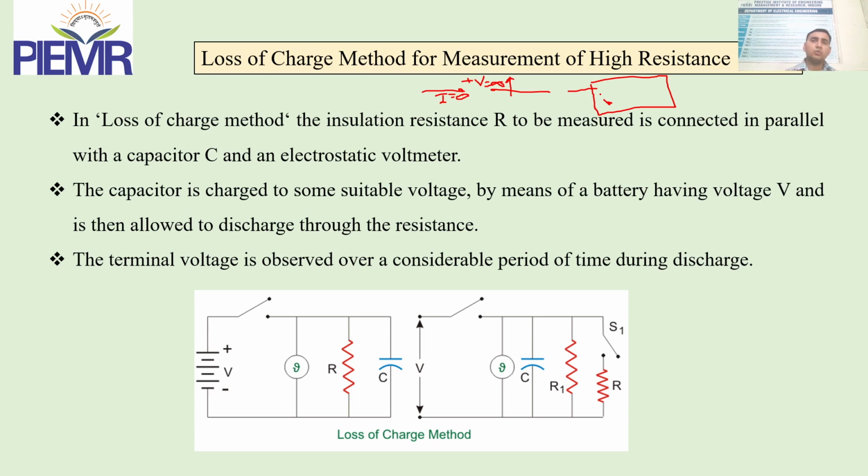We connect one lead to the upper surface and one lead to the stator winding, and measure the resistance. If the resistance between them is very high, approximately hundreds of mega ohm, there is no connectivity between them. One method we suggest for this measurement is the loss of charge method.